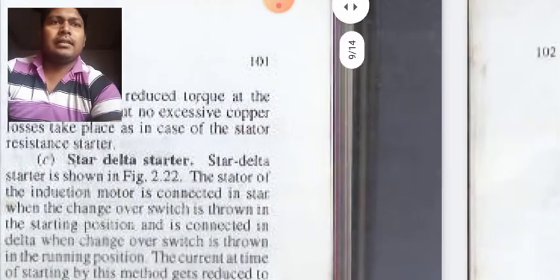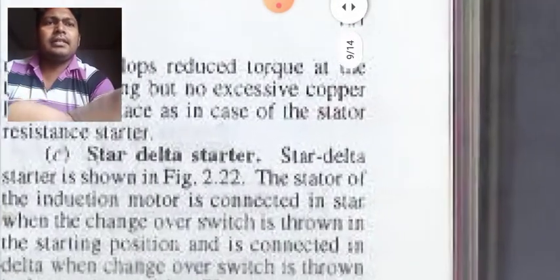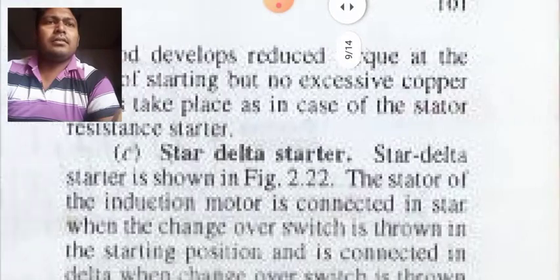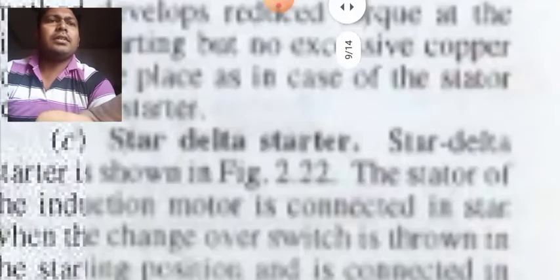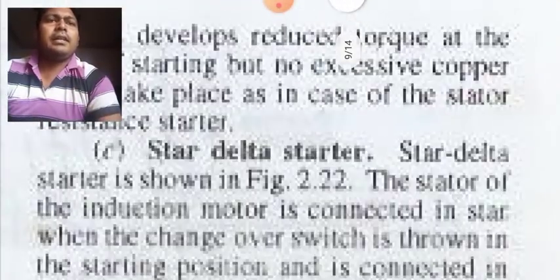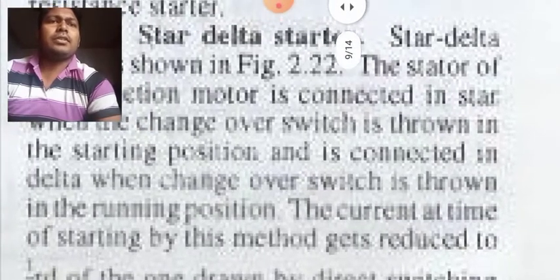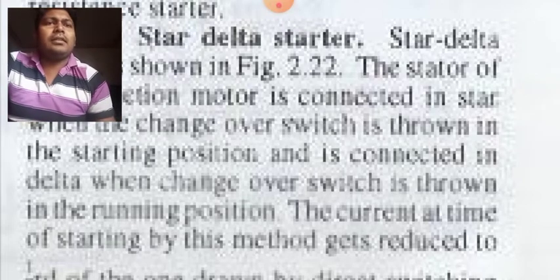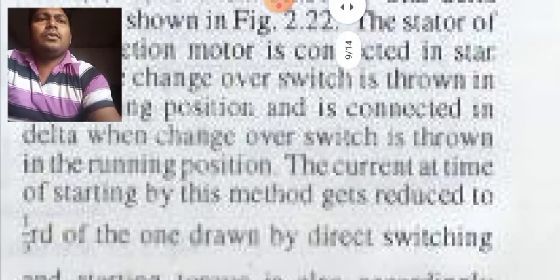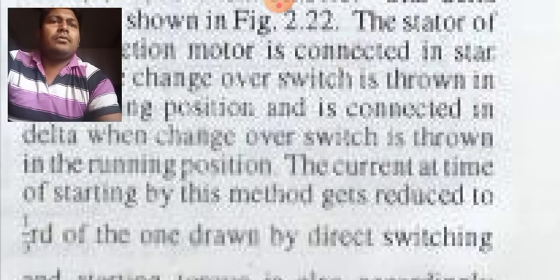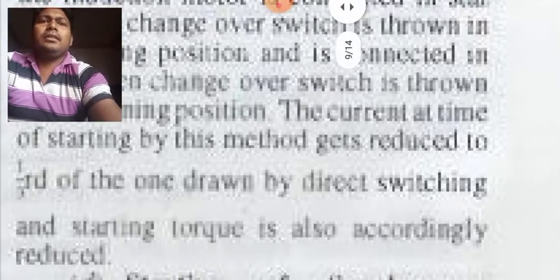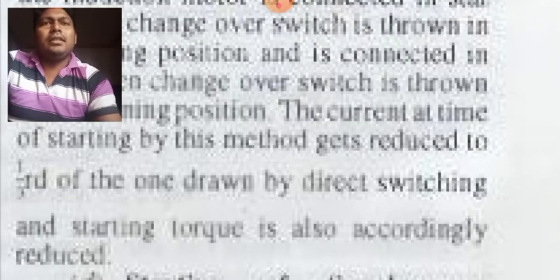Star delta starter is as in the diagram which we have just seen. The stator of the induction motor is connected in star when the changeover switch is thrown in the starting position, and is connected in delta when the changeover switch is thrown in the running position. So the current at the time of starting by this method gets reduced to 1/3 of the one drawn by direct switching, and starting torque is accordingly reduced.